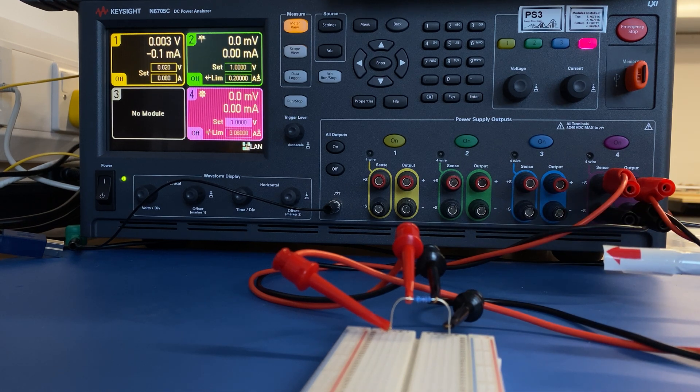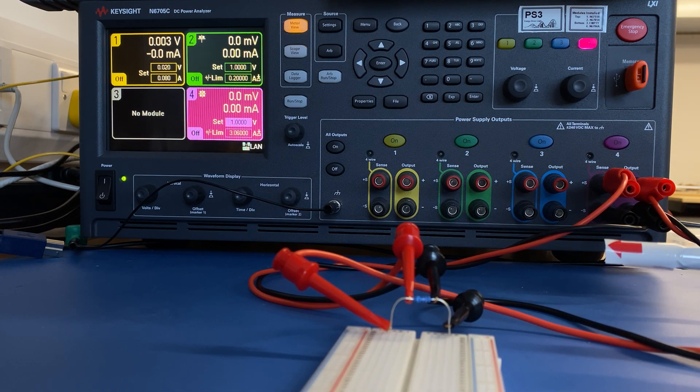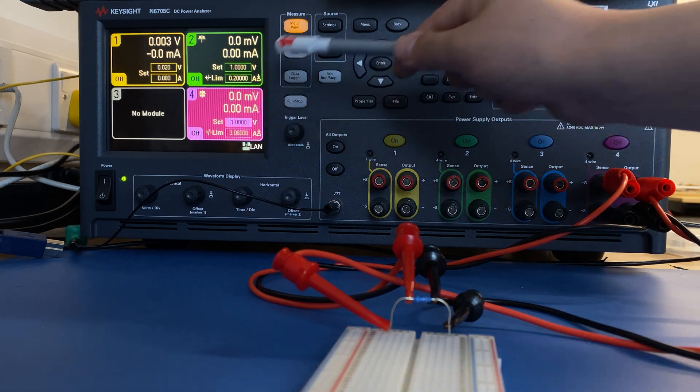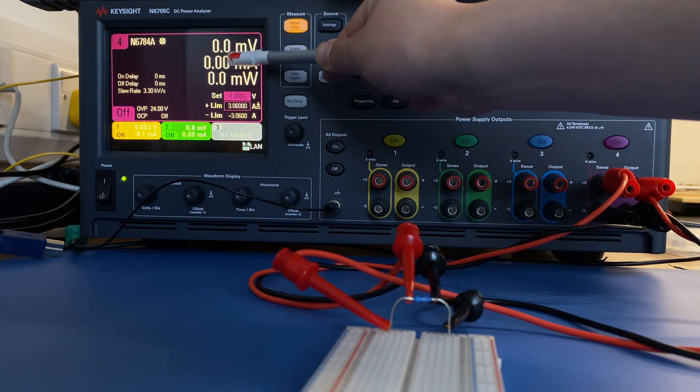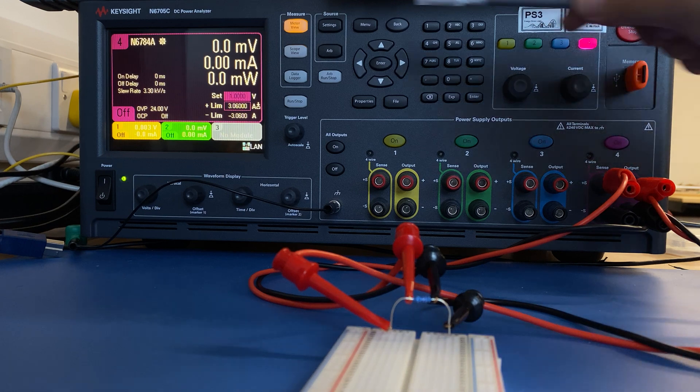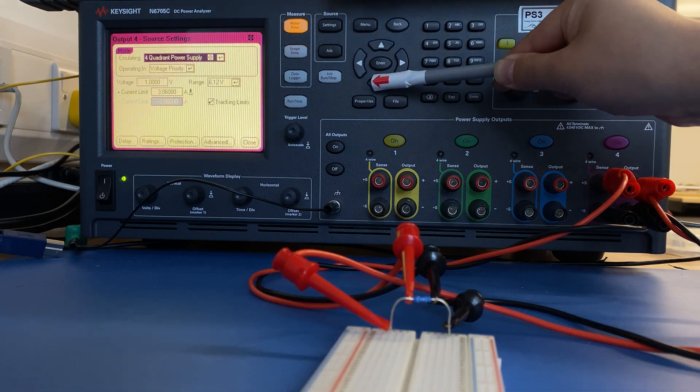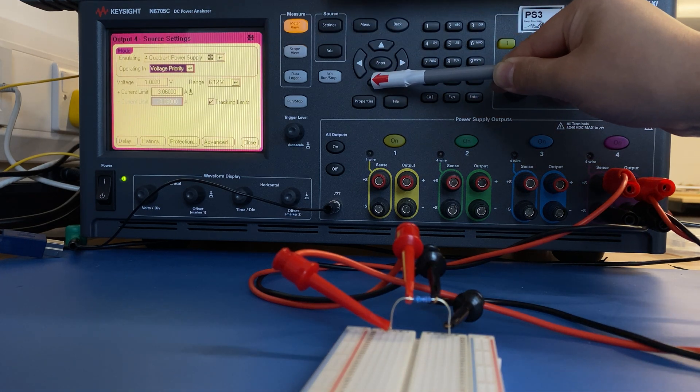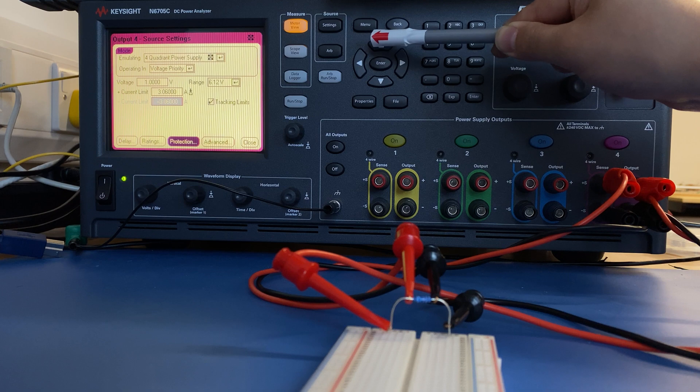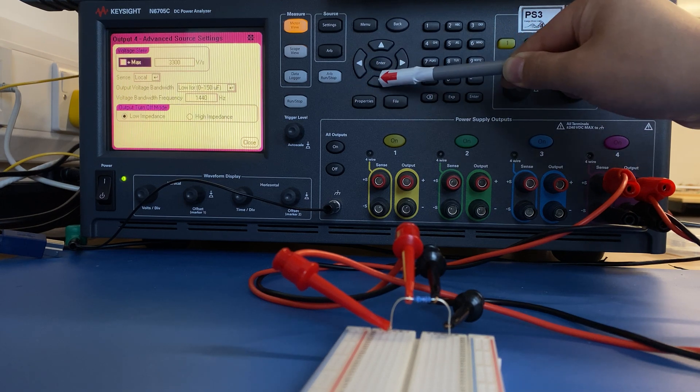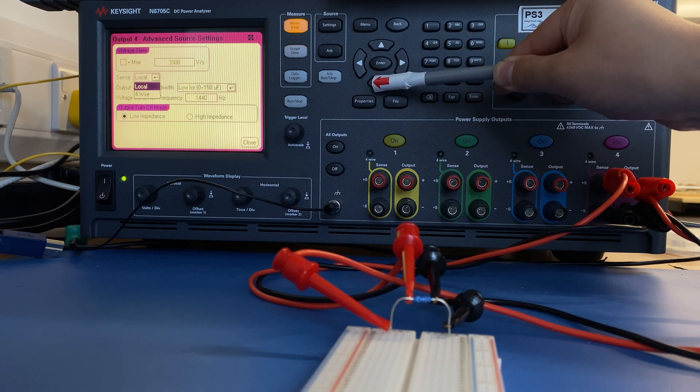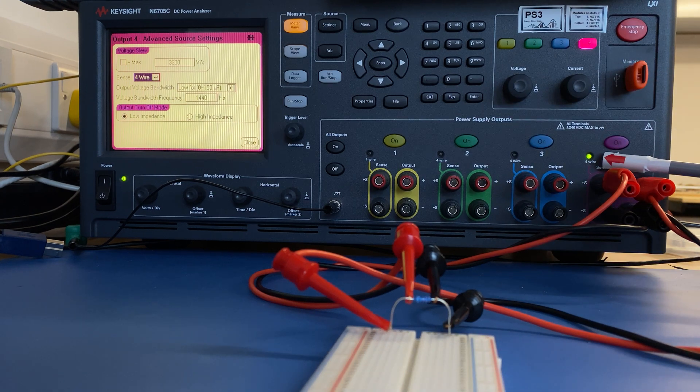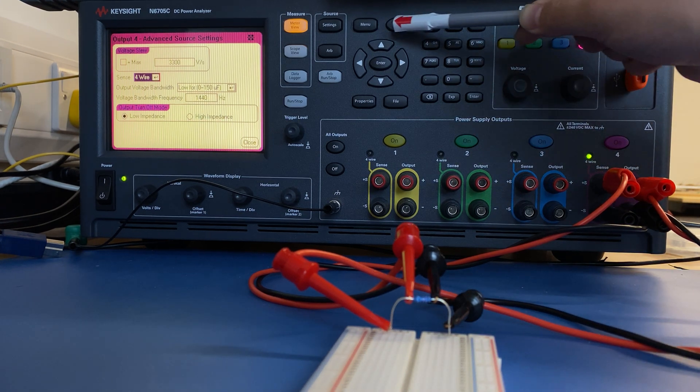So to enable 4-wire setting, you need to go to your channel. For example, in this case, we have channel 4. We go to setting, we navigate to advanced, we enable 4-wire sensing. You will see the 4-wire LED is turned on.